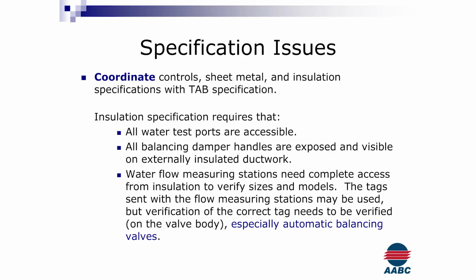Insulation specification requirements are something that comes up, which is why we wanted to put this in. On the water side of tab, we always see the insulators insulate over the valves, and then it's up to us to either cut and break the vapor barrier, which we don't want to do because we're not insulators and we don't carry the tapes and extra insulation with us. So it's important to catch in the spec what you're expecting other contractors to do to make the tab go—at least be applicable to the job.